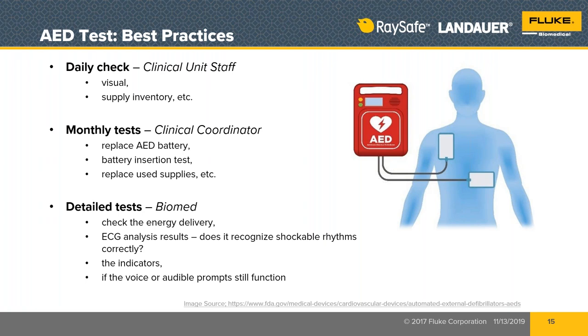Well, I would just say if you're going to use something not from the original manufacturer, that you keep track of your failure rates and keep a really, really close eye on that, because a lot of times a secondary market and aftermarket battery is not the same as the battery that was tested and validated in the process of getting their FDA clearance to market, especially in the United States. There is no medical device that's sold in the United States that is able to be sold without a US FDA clearance to market. And that clearance includes all of the supplies and accessories that are to be used with that medical device.